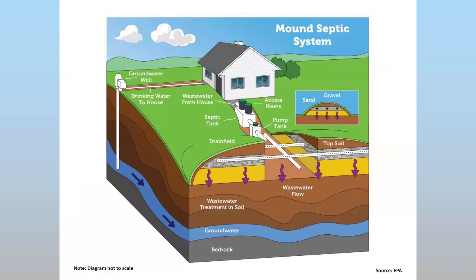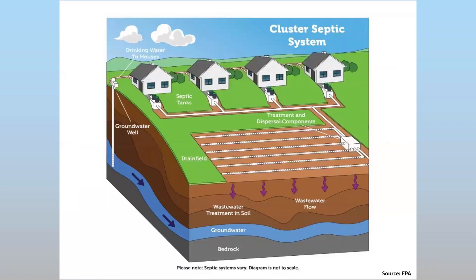There are also opportunities for shared drain fields through what's called a cluster system. Each individual home has its own septic tank, and effluent is either gravity-flowed or pumped to a shared soil distribution system — whether gravel trenches, drip irrigation, or other methods. This allows smaller lots to do some initial collection, storage, and treatment before the wastewater enters a community system.